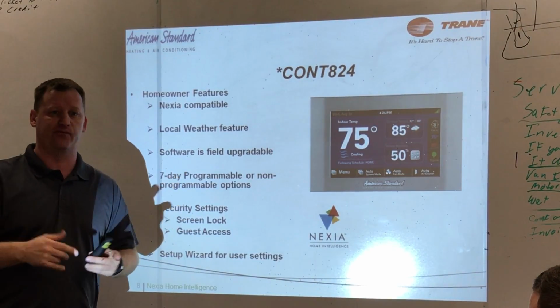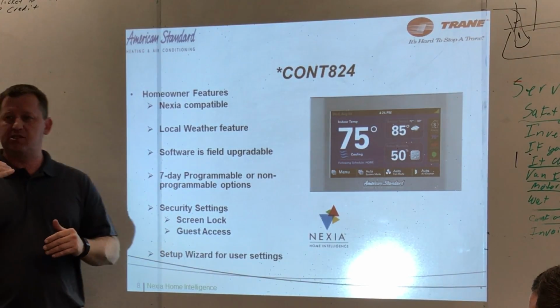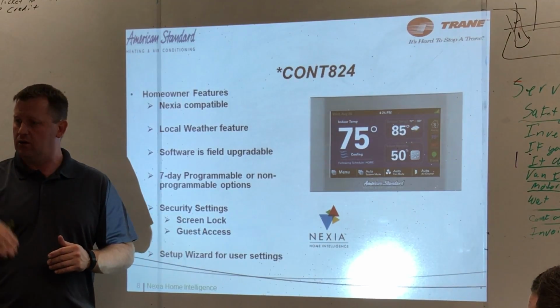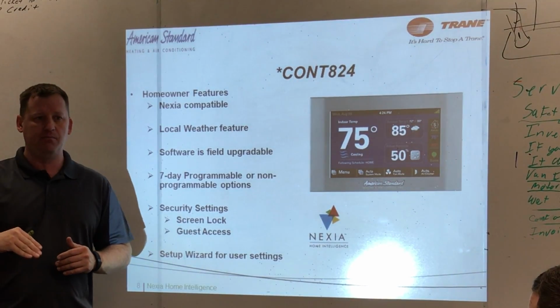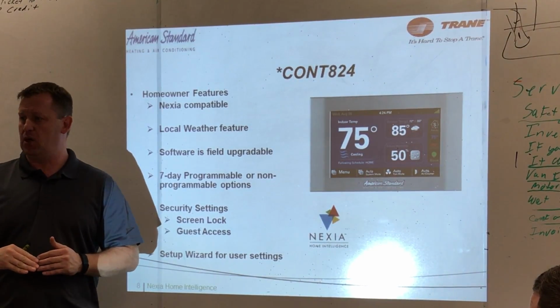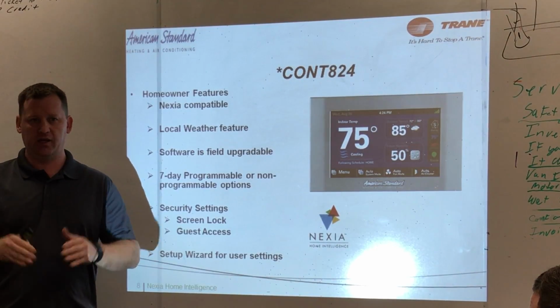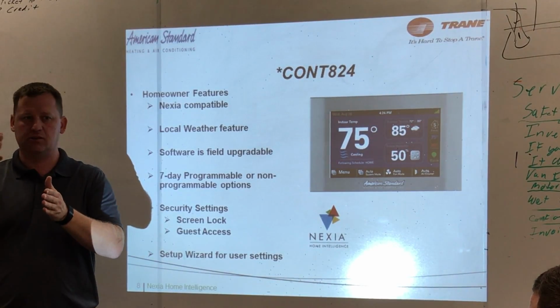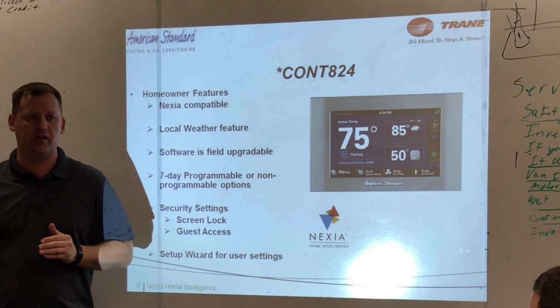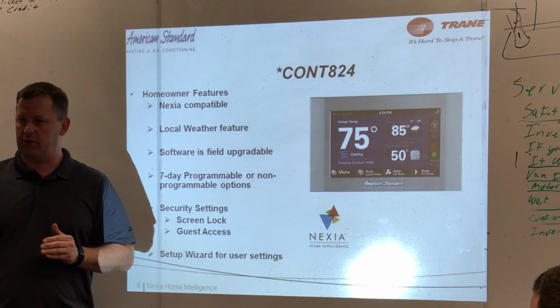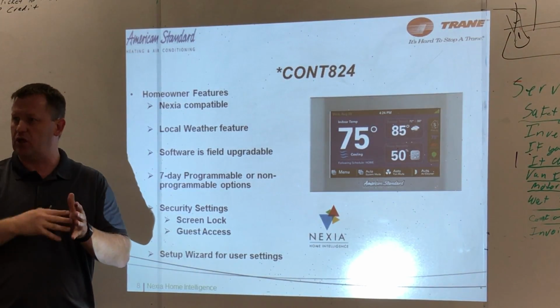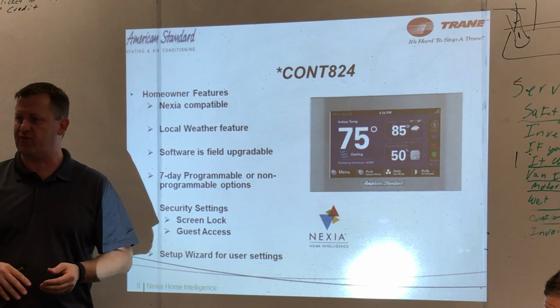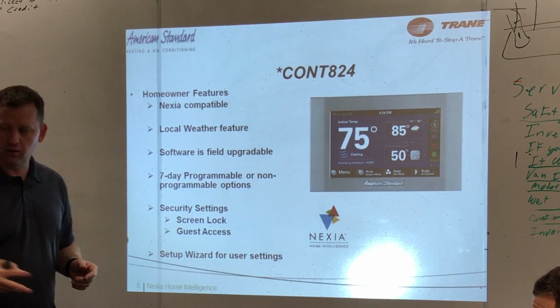Then you can see that information. Or you can see at 5 o'clock every day during the summertime, their set point's creeping off, and it does it every 30 minutes because the outdoor unit gets shut off by the power utility provider. Because some of them have the little shutdown device that they get $5 off their power bill - load shedding or something. So you can actually see that.